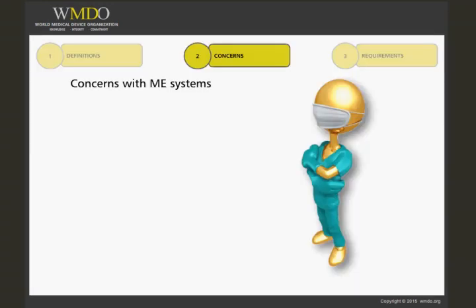The concerns with medical electrical systems are the following. Use of an MPSO, or multiple socket outlet, accumulating leakage currents. If you have multiple devices plugged into the same outlet strip, it will sum the earth leakage currents, potentially leading to an excessive leakage current that exceeds the limits specified in the standard.